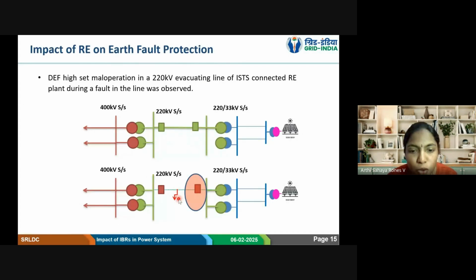There was a fault in this line, the 220 kV evacuating line itself. This line I'm calling an RE evacuating line. This portion is grid and then only RE is connected. So this is what I'm calling the 220 kV evacuating line. In the next case, there was a fault in this particular 220 kV evacuating line. During this time also the same thing happened. From the grid end, we had actual fault current contribution, whereas from the RE end we saw the zero sequence current.